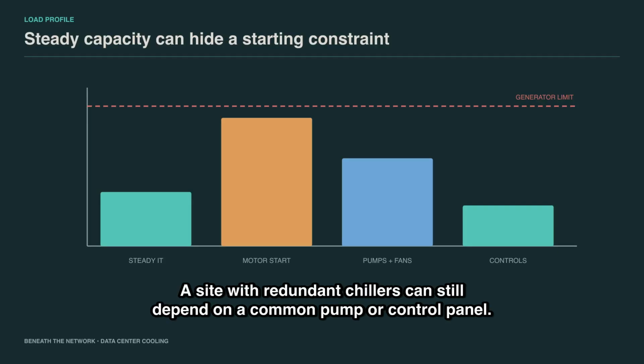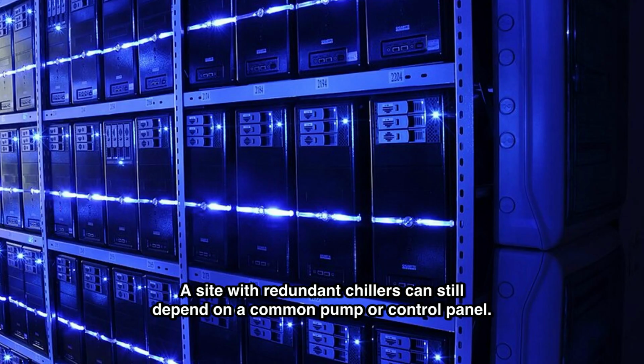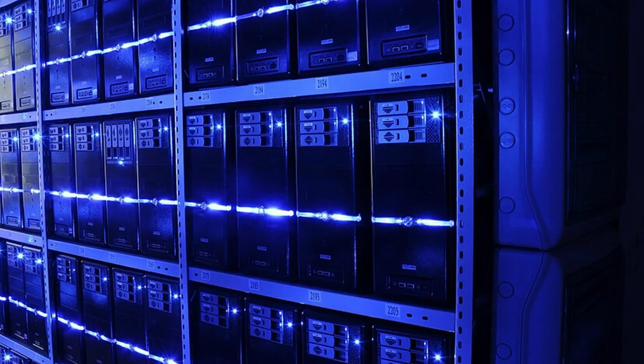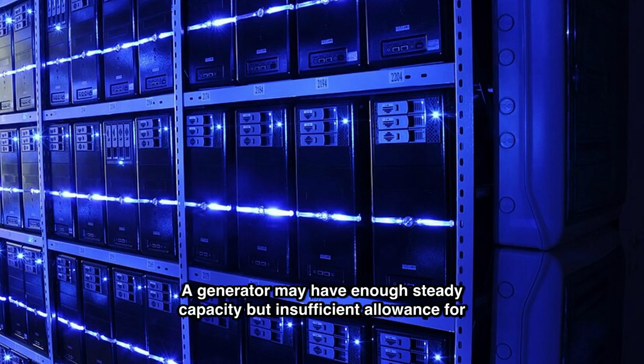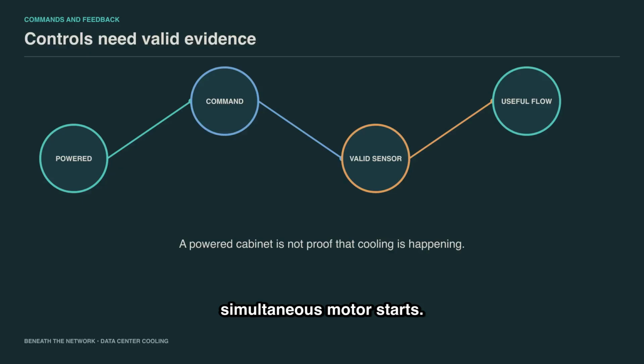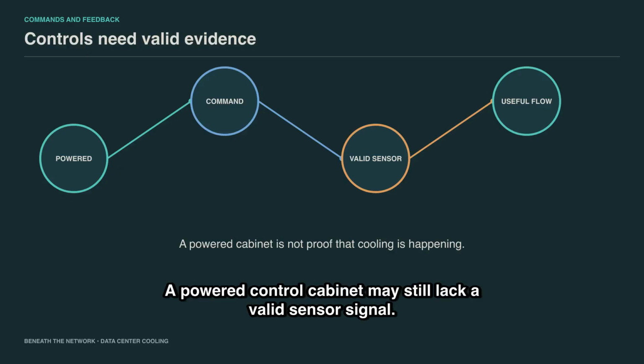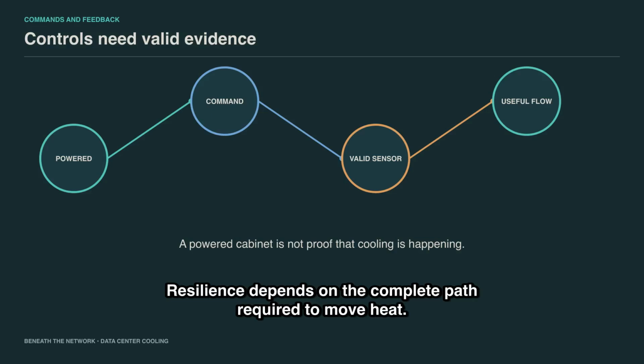A site with redundant chillers can still depend on a common pump or control panel. A generator may have enough steady capacity, but insufficient allowance for simultaneous motor starts. A powered control cabinet may still lack a valid sensor signal. Resilience depends on the complete path required to move heat.